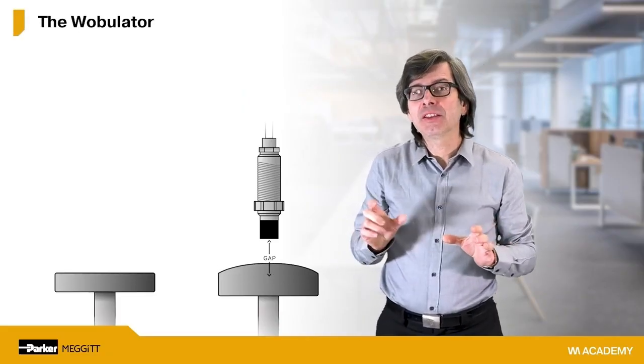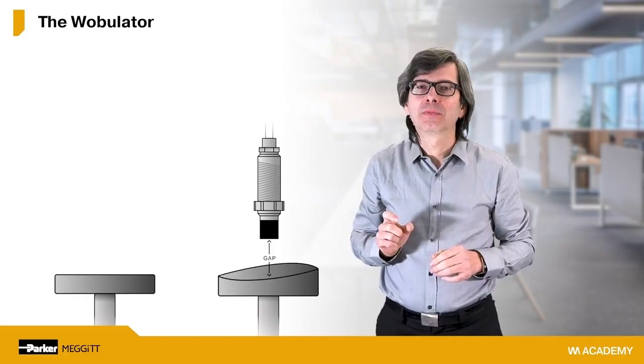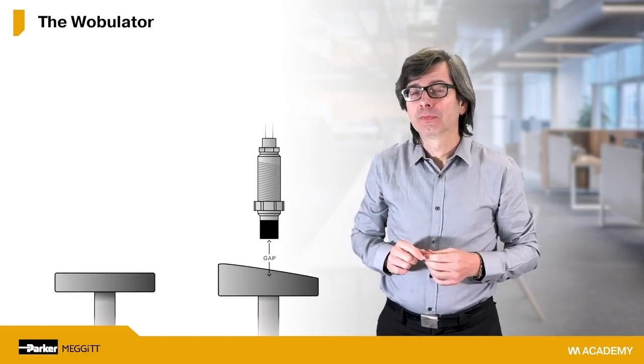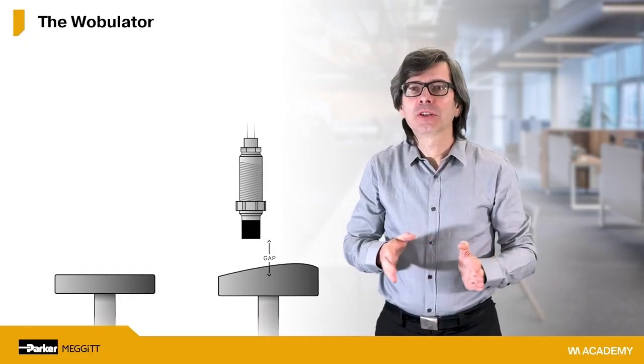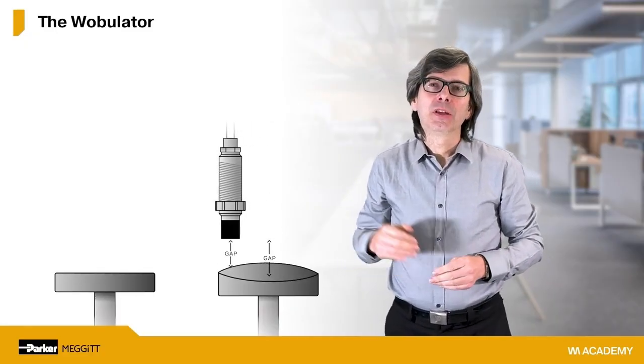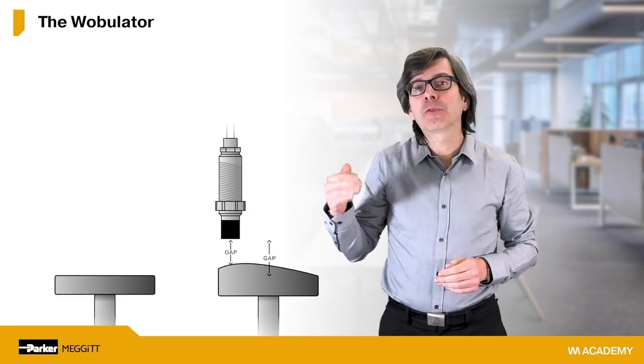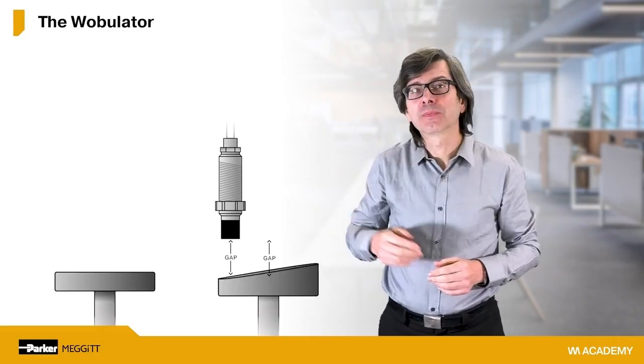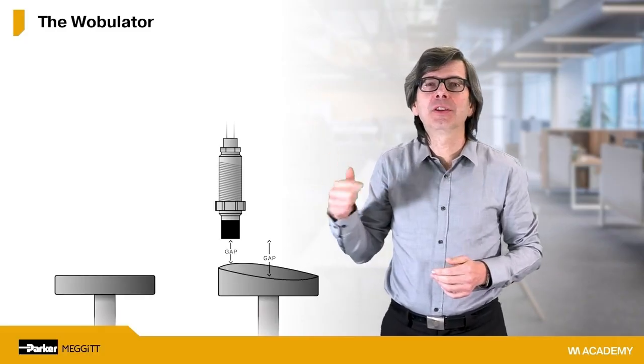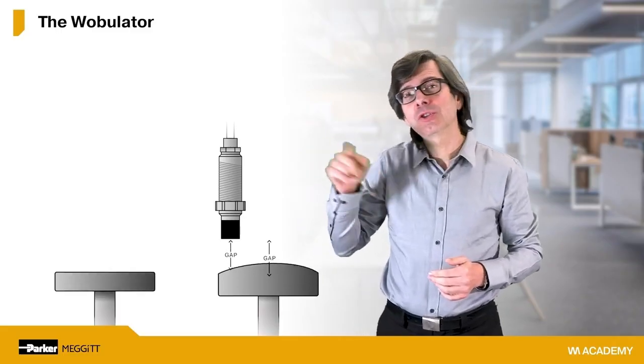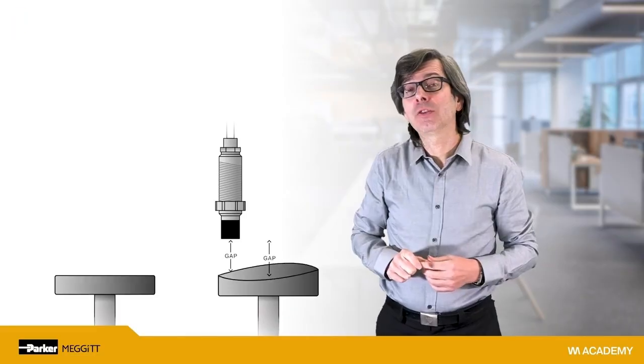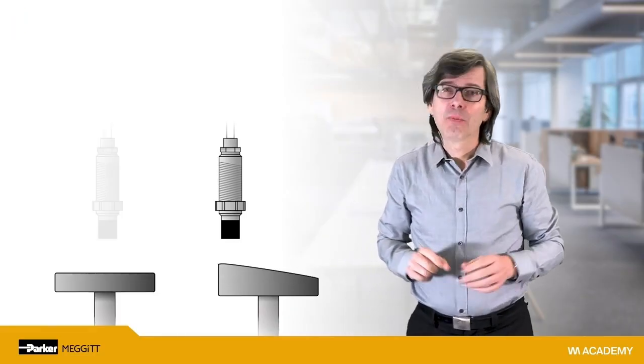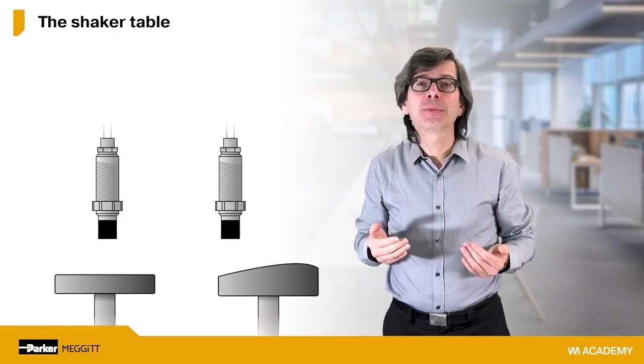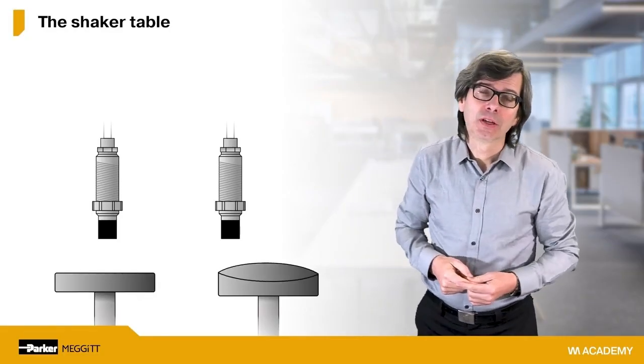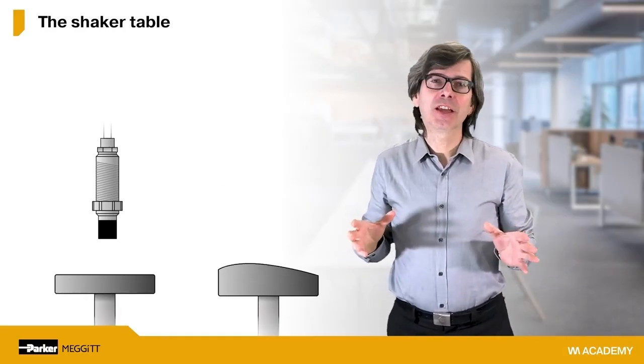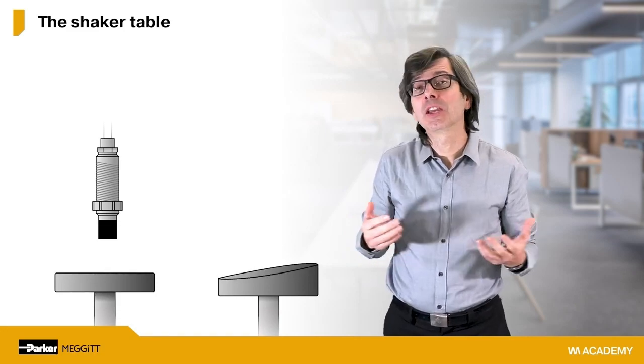With the probe in the center of a wobulator's rotating plate, the probe will observe no vibration at all. However, as the probe is moved toward the outer diameter of the plate, the wedge shape results in a greater changing gap as the plate rotates, and the short end of the wedge passes under the probe, followed half a rotation later by the long end of the wedge. Both the wobulator and the shaker table methods are commonly used in the field. An advantage of the shaker table, however, is that it can be used for checking more than just proximity probes.